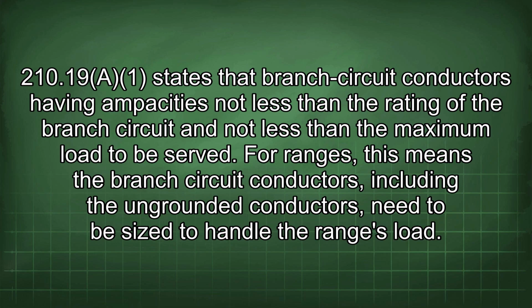210.19 A states that branch circuit conductors must have ampacities not less than the rating of the branch circuit and not less than the maximum load to be served. For ranges, this means the branch circuit conductors, including the ungrounded conductors, need to be sized to handle the range's load.